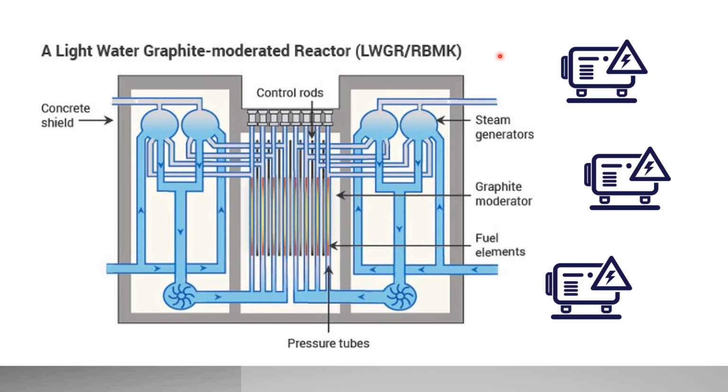There was a potential safety risk there. If a blackout occurred and one coolant pipe burst, there may not be enough time for the generators to reach the max power output. And this would be needed to compensate for the lost water due to evaporation.